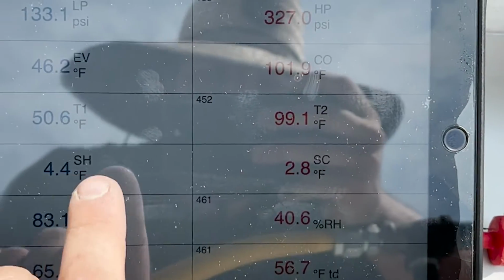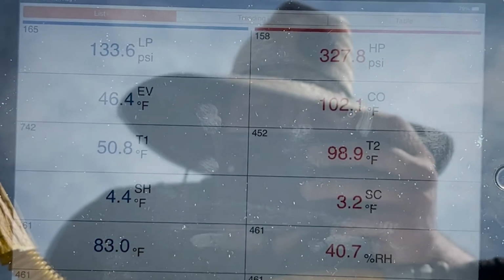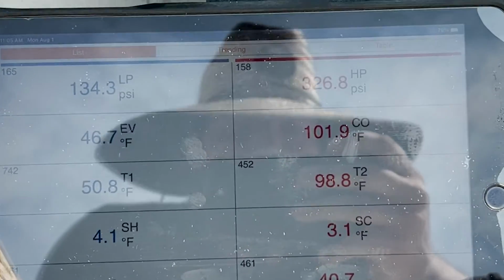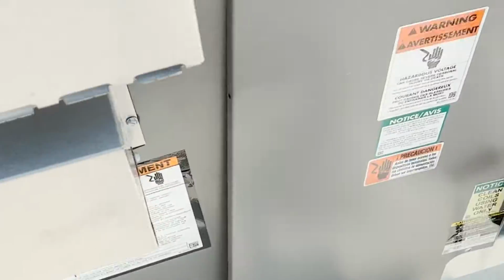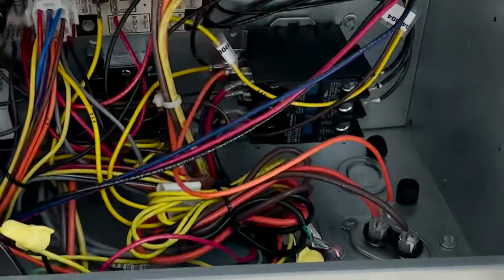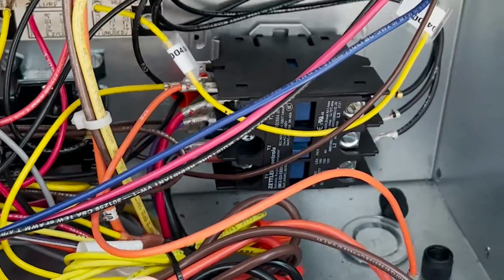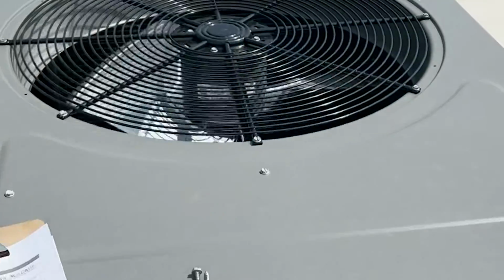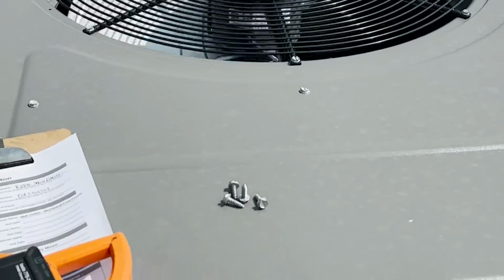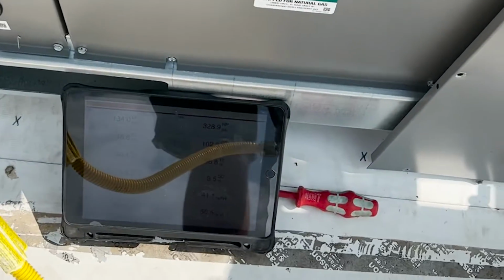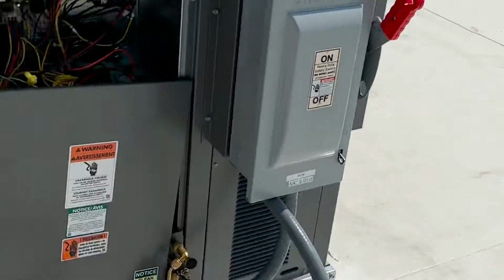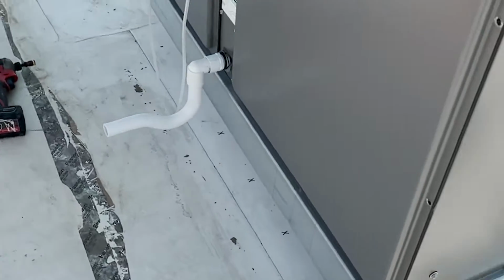All right, as we let this come around, and we wanna let it run for a minute, because if we just document it in the first minute of runtime, we're gonna document issues. So we need to let this run for 10-15 minutes. Which gives us a great opportunity to come through and do our amp readings, right? So we can get our amp draws on the compressor, we can get our amp draws on our blower, we can get our amp draws on our condenser fan motor, all while this is getting time to stabilize. And I guarantee you the guys inside on this job site are pumped.